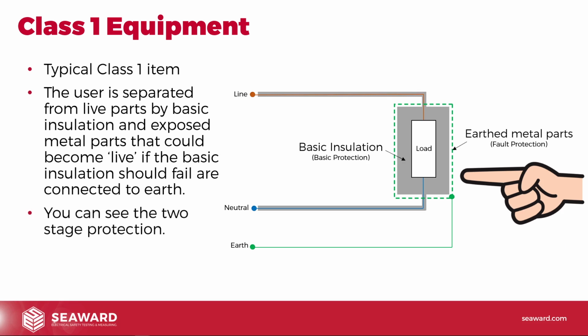We've got the basic insulation providing the basic protection. That's what's protecting us all day, every day under normal conditions from the things that are meant to be live. If there's a fault with the basic insulation, then we've got earthed metal parts. We earth the metal parts, and that provides the fault protection. So if the metal parts were to become live, straight away that fault current would be diverted down to earth, and that would operate our fault protection within the main electrical installation. So your circuit breaker would trip, your fuse would blow, or your RCD would trip.